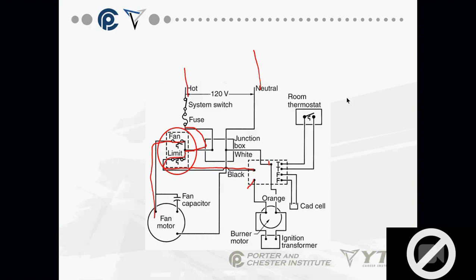Anybody? It's okay to be wrong. Ignition transformer down at the bottom. No, that's my ignition transformer. Where's my transformer for my low voltage thermostat? I'm not seeing it anywhere. Believe it or not, it's in that primary control. Okay, this primary control contains my transformer.